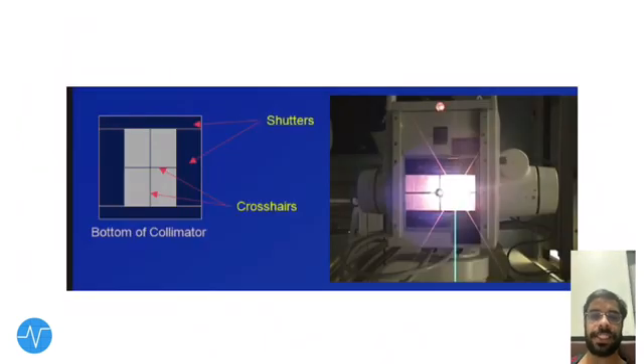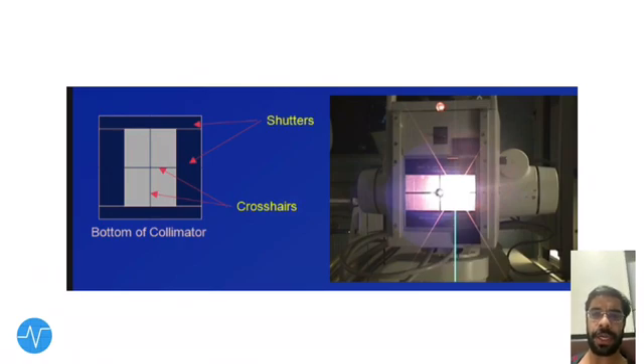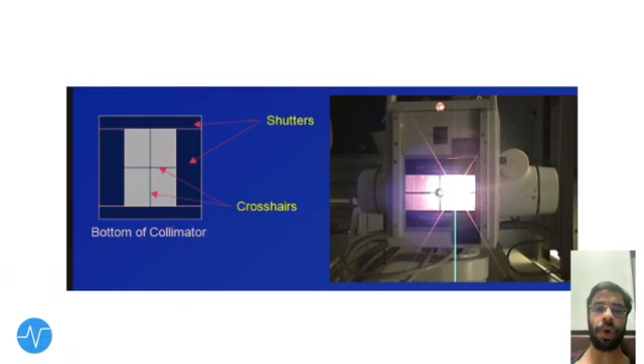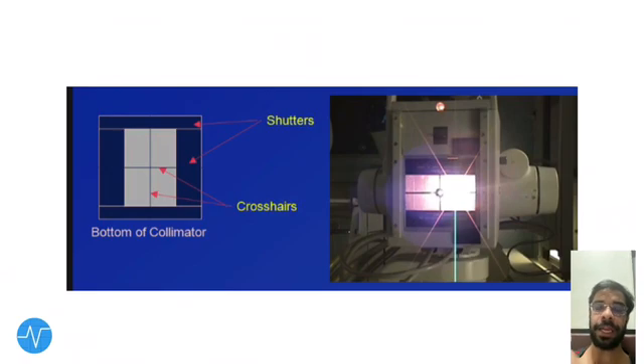In the image, we can see two diaphragms with shutters that can be adjusted to control how much width or opening is needed. This collimator is placed between the glass tube and the patient, and it restricts the shape of the x-ray beam.